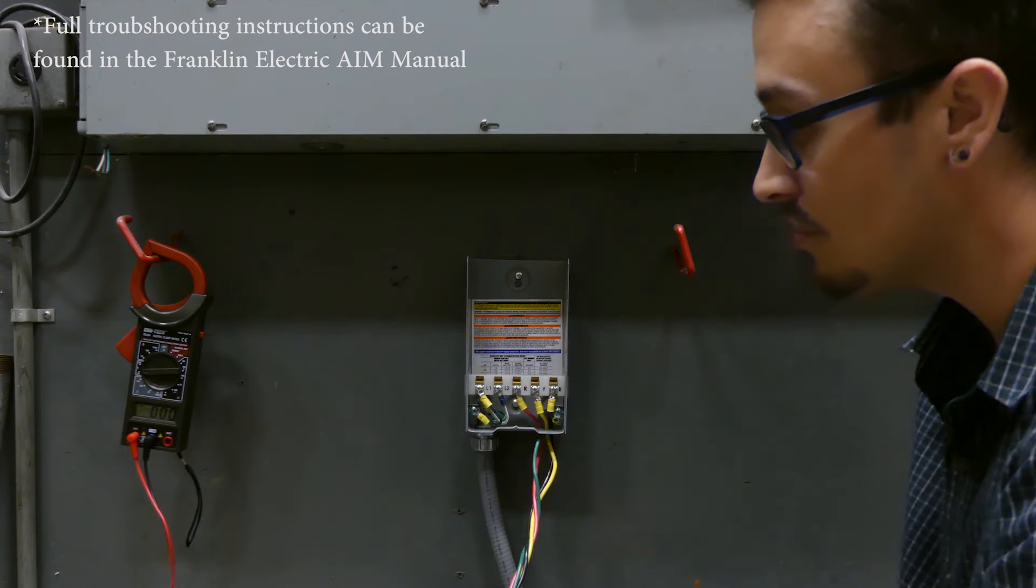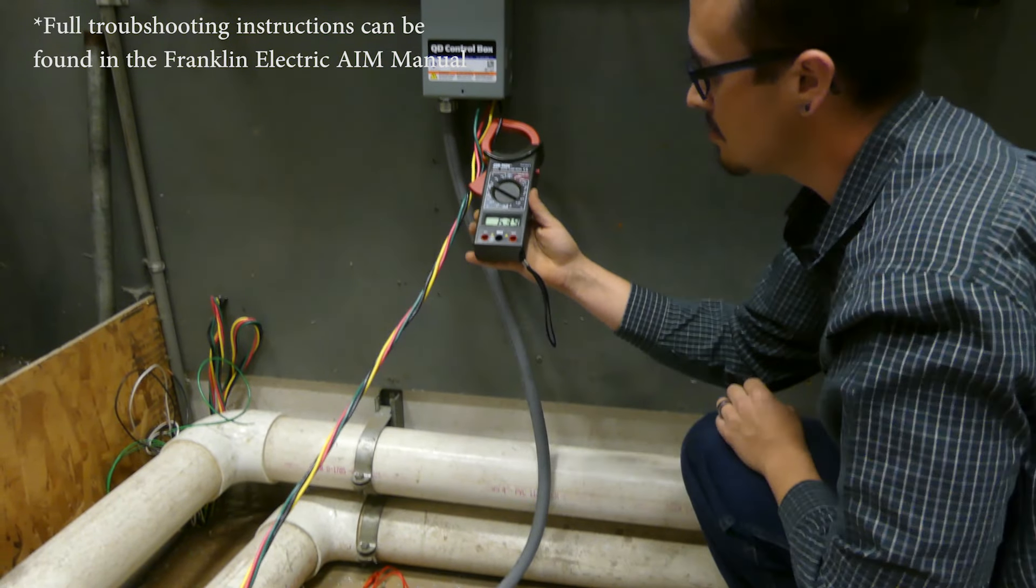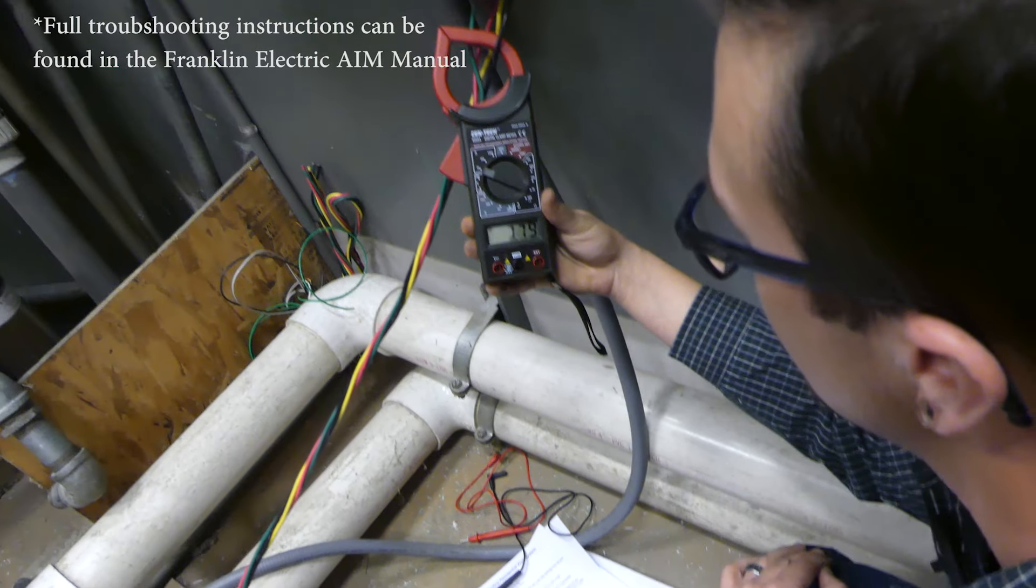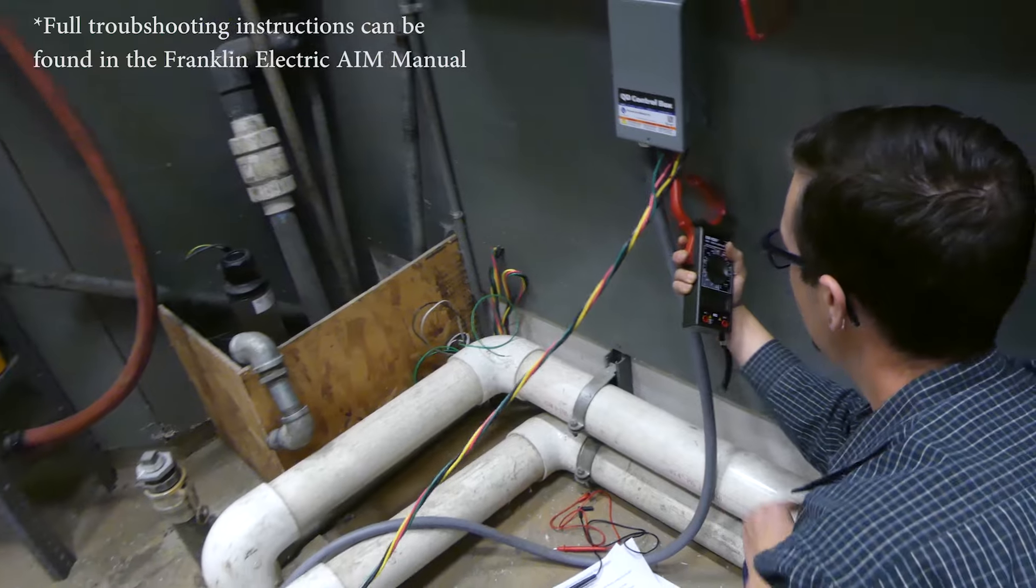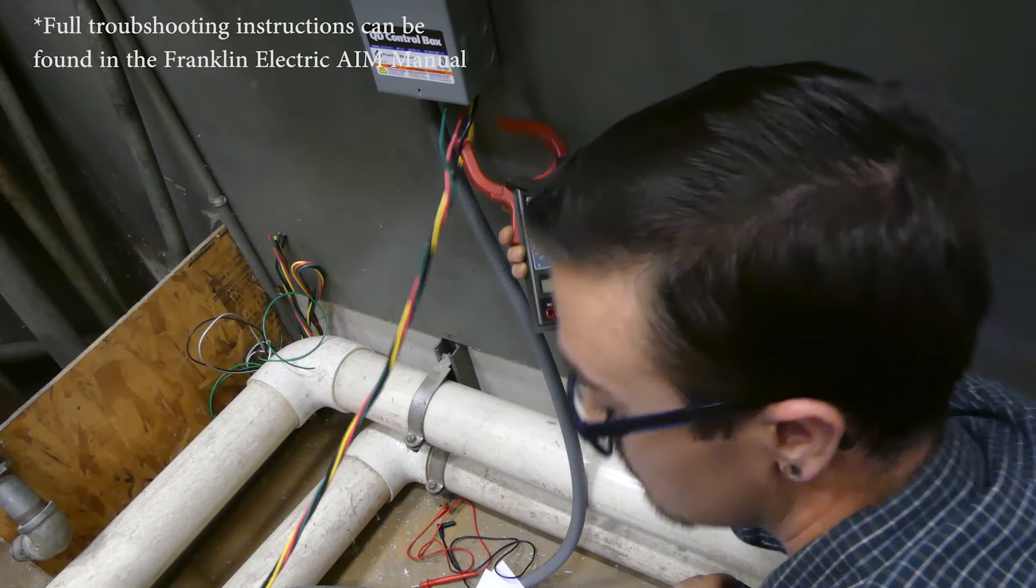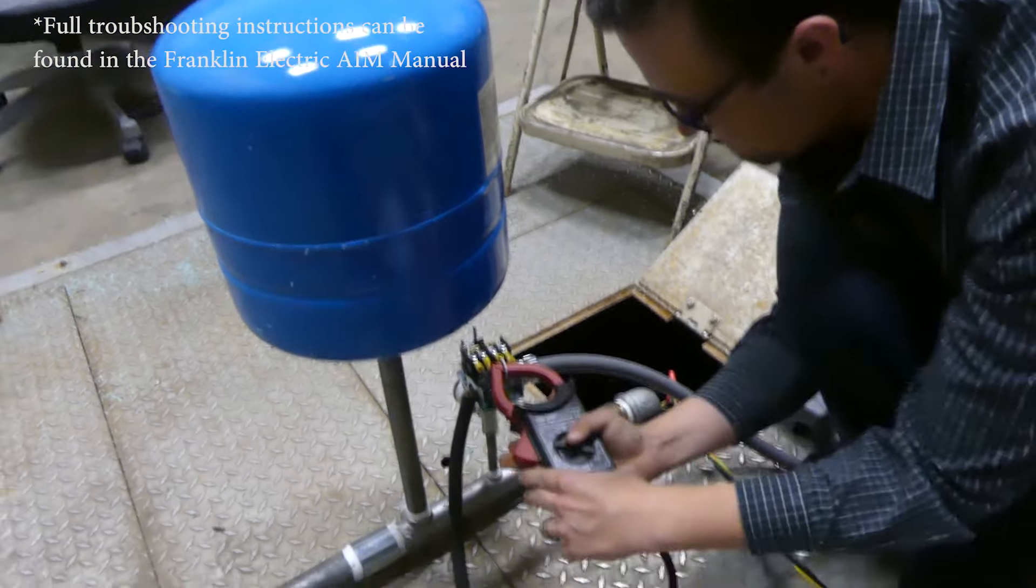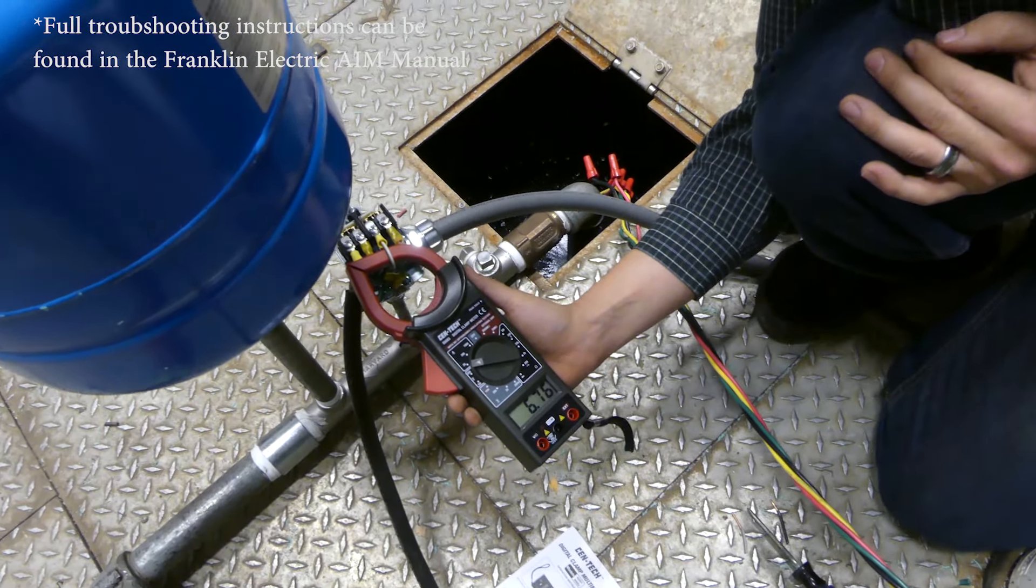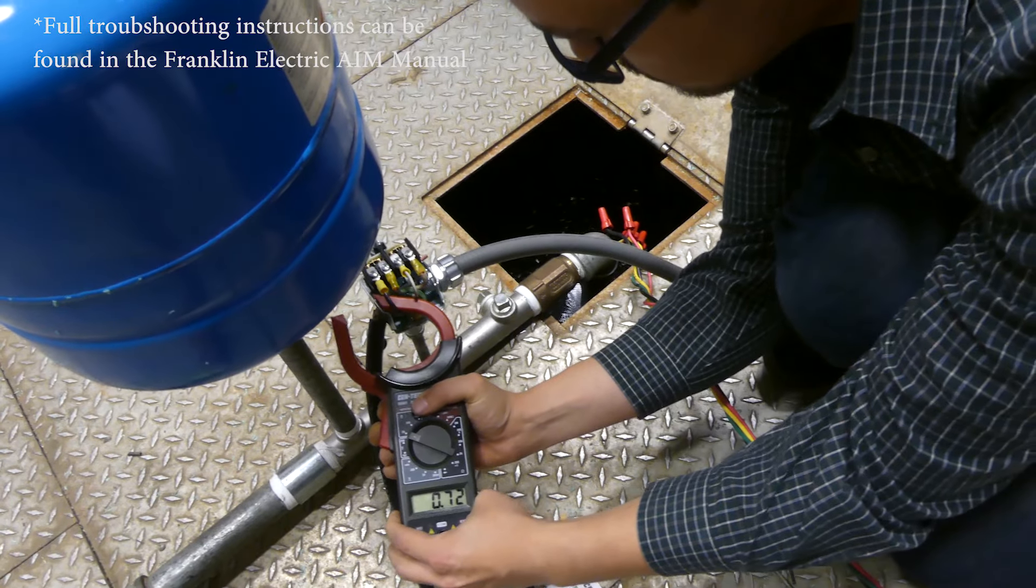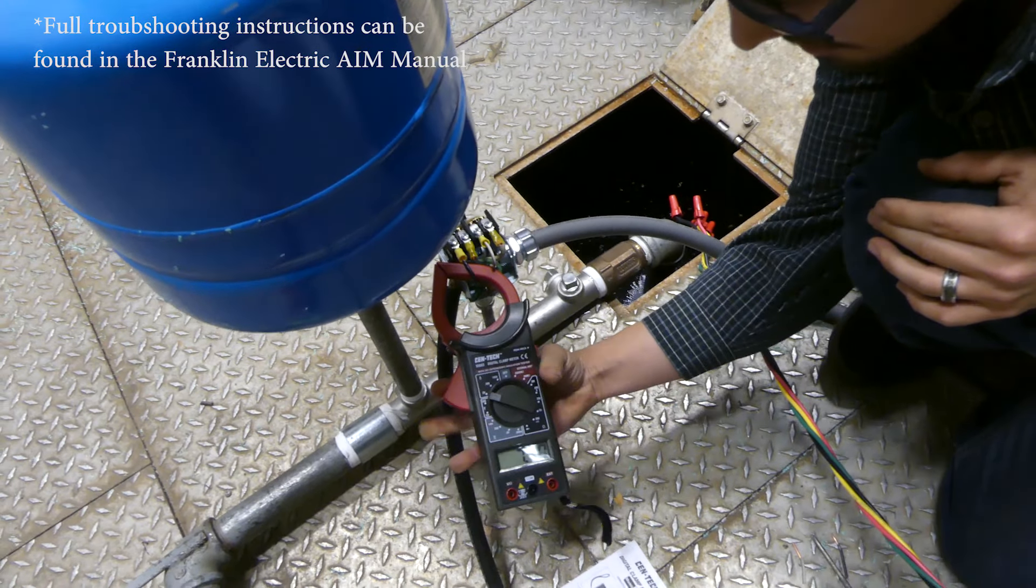Now we need to throw the face back on this panel and let the pump run, and we'll take an amp reading on this pump. About 7.8, about 6.8, which matches, and about seven or so. We're good to go.